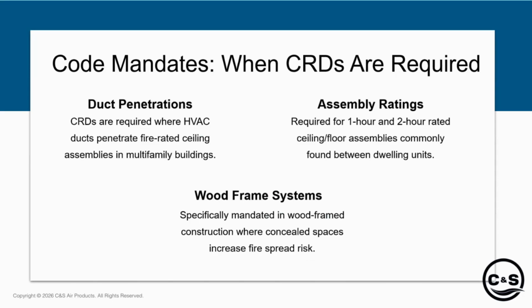Code. So when CRDs are required, we've gone through some of the generalities of, hey, anytime there's a penetration in the ceiling space, you have to put a ceiling radiation damper there. But in the scope of numbers, somewhere between 6 and 10 to 12 penetrations per apartment space is typically what you're going to see in each different unit. So these things can multiply quickly.